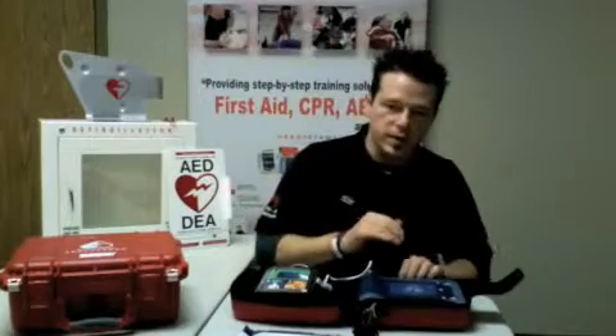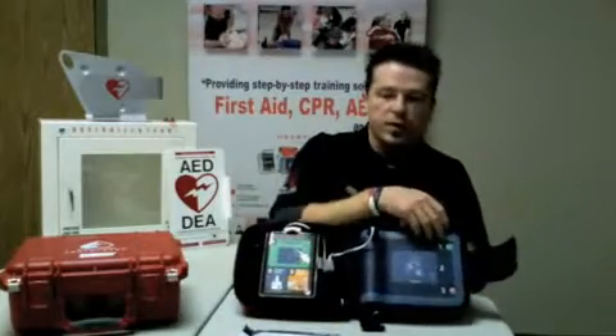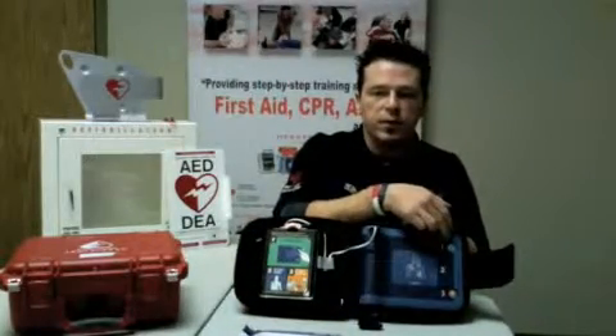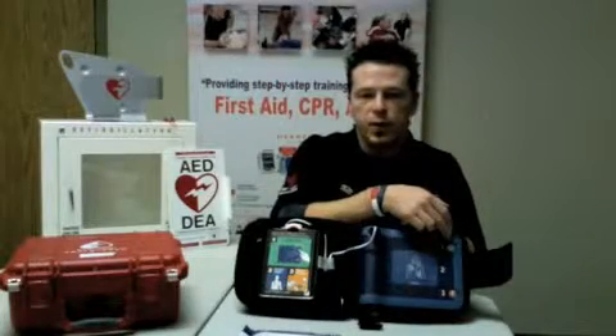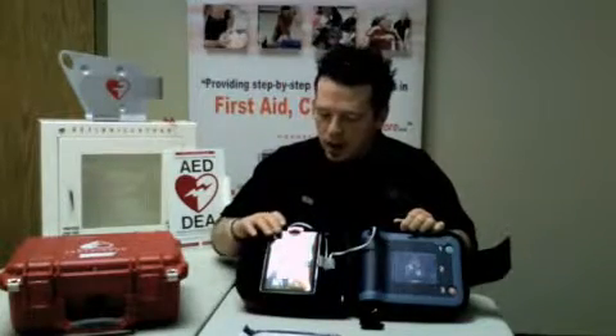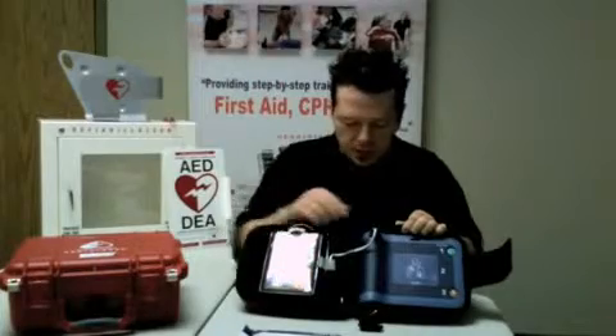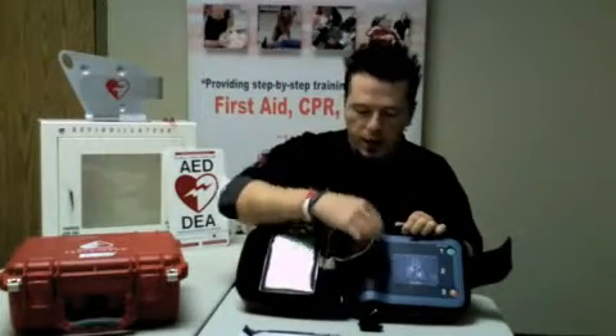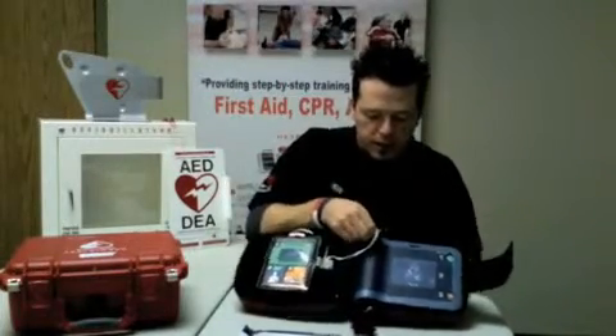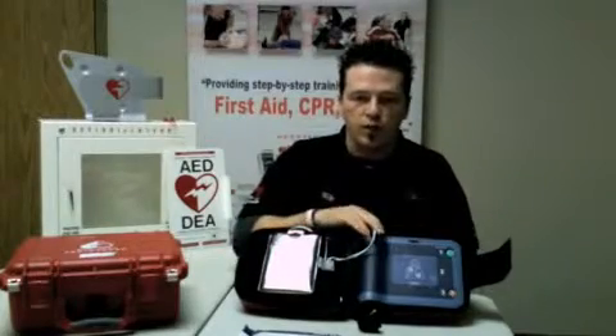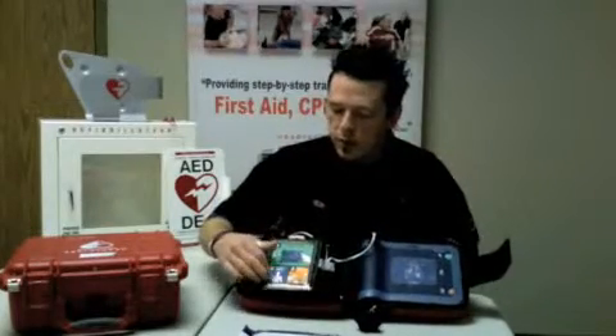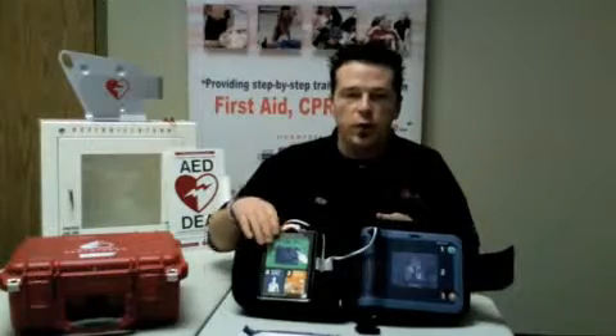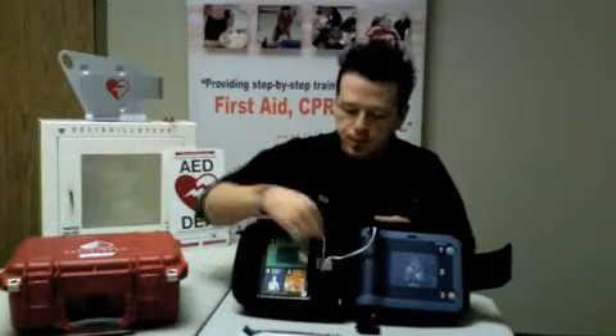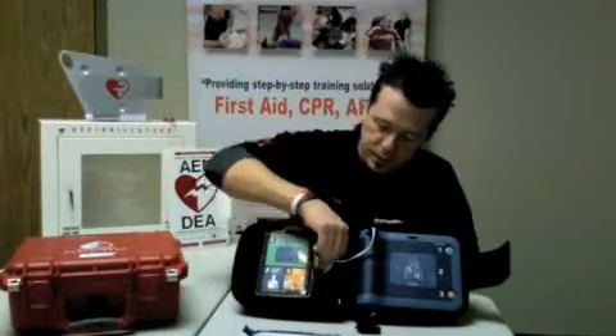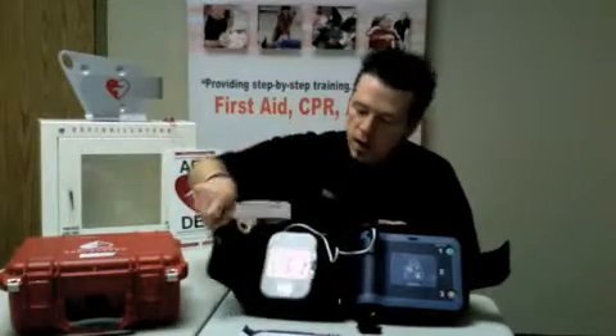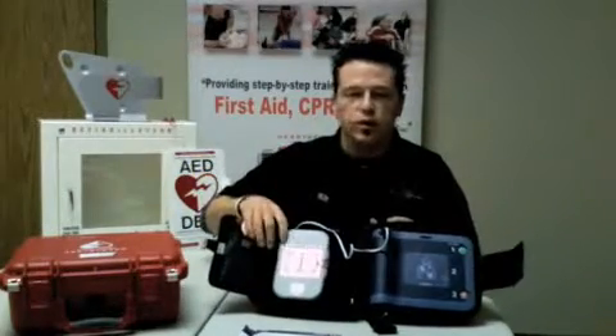Now again, in this scenario, the defibrillator is in working order because this green flickering light is working. It is flickering every 4 to 5 seconds. Another quick visual is that you'll notice there is a wire that shows that it's plugged in, which means that the electrodes are ready to be used. And you'll notice that there's a quick reference guide, which will be useful if you ever have to use the defibrillator. Taking this little gray piece of material and pulling up on the Velcro, you'll access the electrode pads.